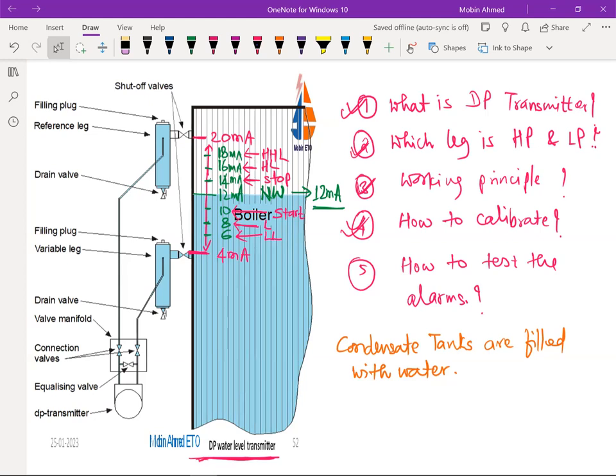We will shut off. Come again, please. The shut-off valves we will close first. Yeah, that is okay, the shut-off valves we have closed now. Then for the high level, this filling plug we will use. Then in the reference leg we will fill, so it will show the high level alarm.